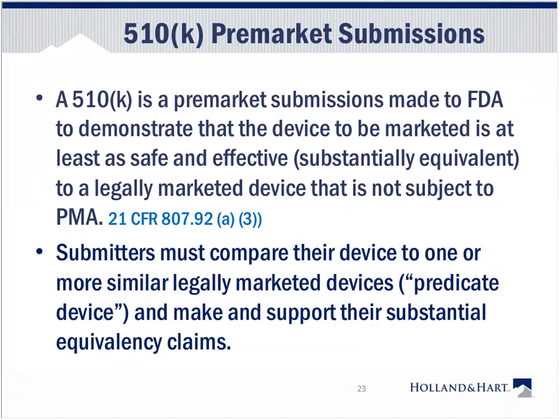So the 510K is a pre-market submission made to the FDA to demonstrate that the device to be marketed is at least as safe and effective, substantially equivalent, to a legally marketed device that is not subject to PMA. Again, now we're dealing with devices that do not have to go through the pre-market approval process. That is the highest level of scrutiny, usually involving validated scientific research or clinical study. To get a 510K clearance from the FDA, the easiest way to do it is to prove that the product you're putting onto the market is substantially equivalent to another device that has already been cleared by the FDA. Submitters must compare their device to one or more similar legally marketed devices, which we call predicate devices, and make and support their substantial equivalency claims.